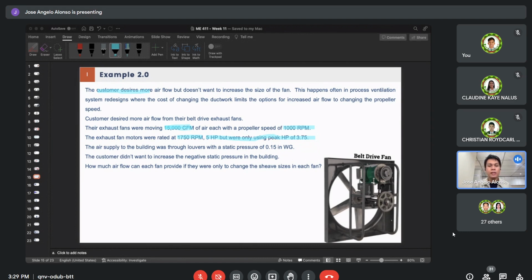The air supply to the building was through louvers with static pressure of 0.15-inch water gauge. The customer didn't want to increase the negative static pressure in the building. So how much air can each fan provide if they were only to change the sheave sizes in each fan? The sheave sizes, class, are just the pulley. This is just our pulley, termed as sheave. So we will only change the sheave size to speed up our fan, or our propeller.